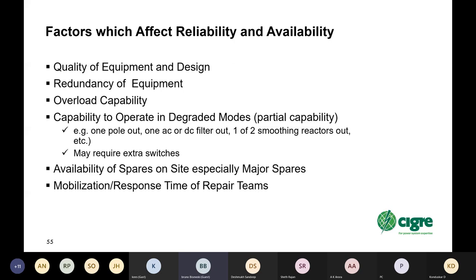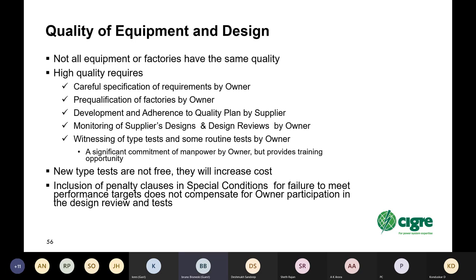Availability or reliability also depends on whether you have major spares on site or any spares on site, as well as the mobilization response time of the repair teams. Looking at quality of equipment, not all equipment or factories have the same quality, and high quality requires a careful specification of the requirements by the owner, pre-qualification of the factories by the owner, development and adherence to the quality plan by the supplier, and monitoring of designs and design reviews by the owners, and witnessing of type tests and some routine tests by the owner.